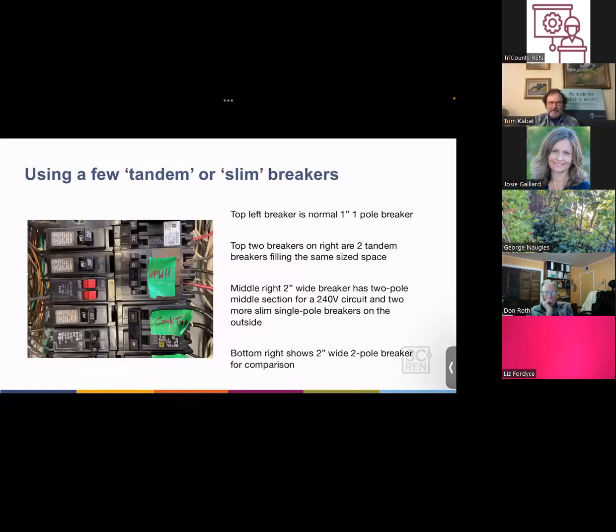Here's a detail on tandem breakers, or slim breakers. You can see on the top left a full width 20 amp breaker, and on the top right a slim breaker with two 20 amp circuits. In the middle, marked HPWH, is my heat pump water heater's 30 amp circuit, with two other circuits on the outside going to other parts of the house. So that shows what a panel can look like with slim breakers and regular fat breakers.